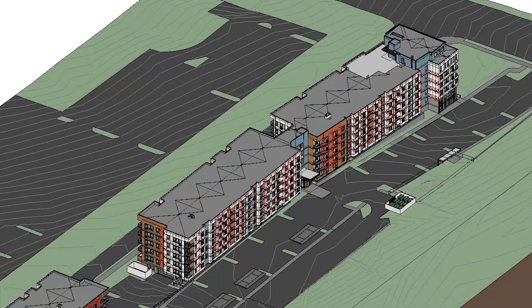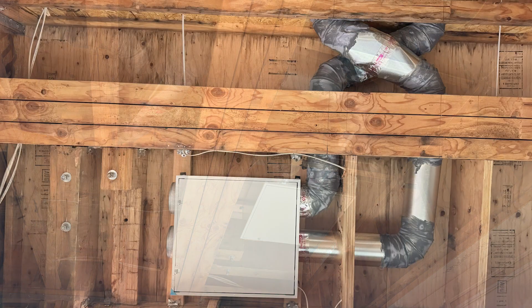The following images are from one recent project example of an ERV installation. At this apartment project, we had to closely coordinate with the structural engineer to determine routing for the ERV ductwork so as not to degrade the structure itself. In addition, the ERV itself is no small unit. This fact alone required structural coordination to allow for room to mount the unit within the joist space. Once a solution was found, this detail was able to be repeated throughout the building.